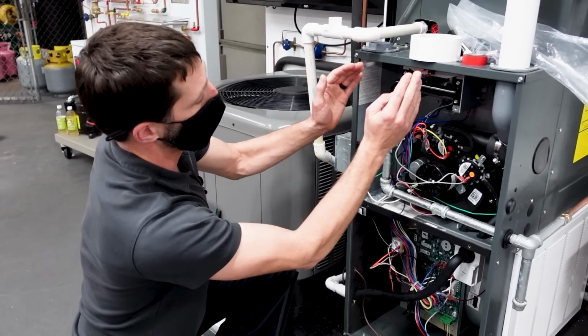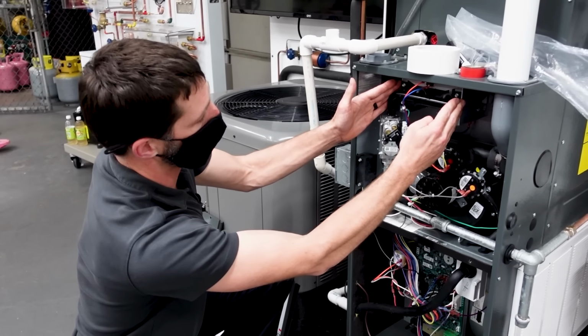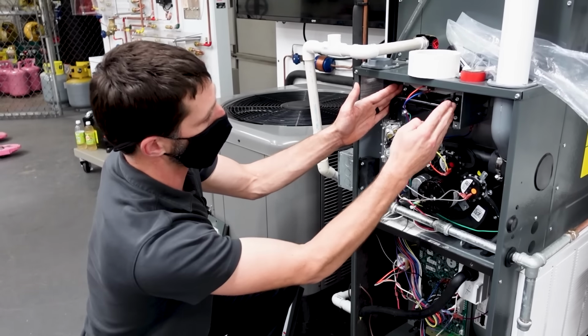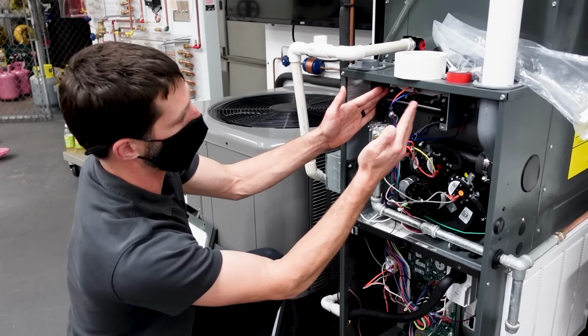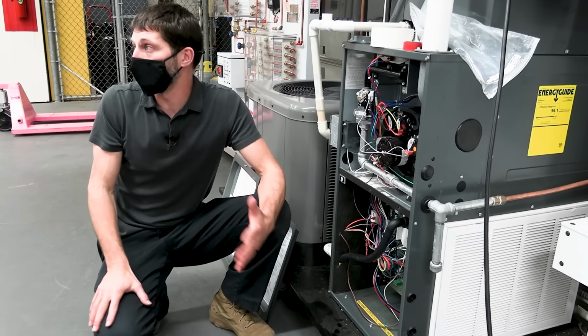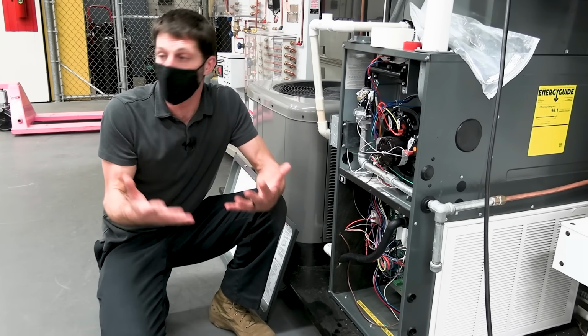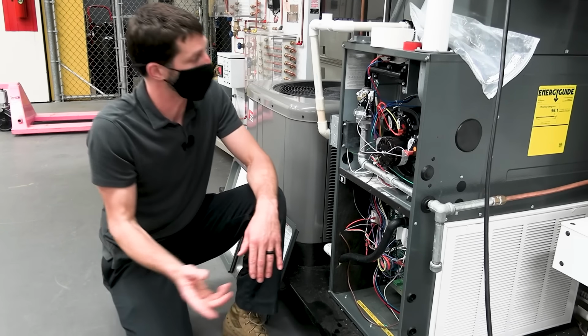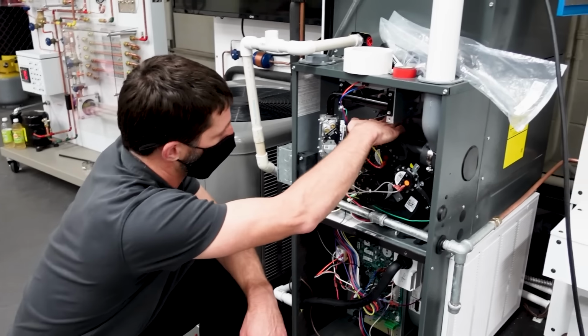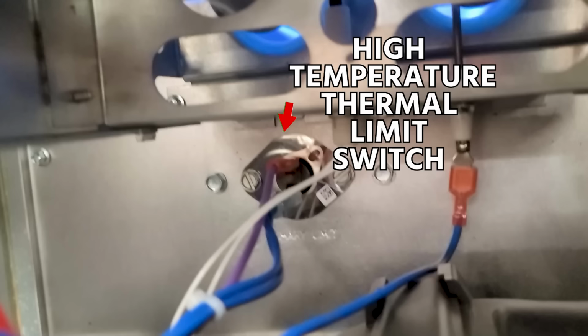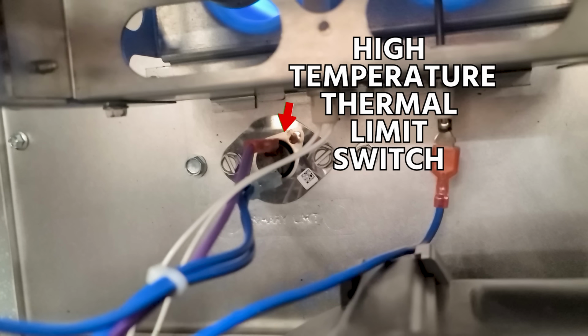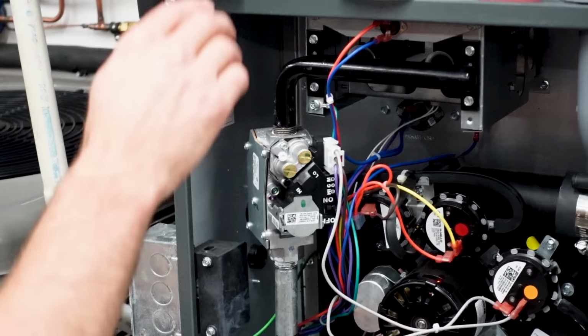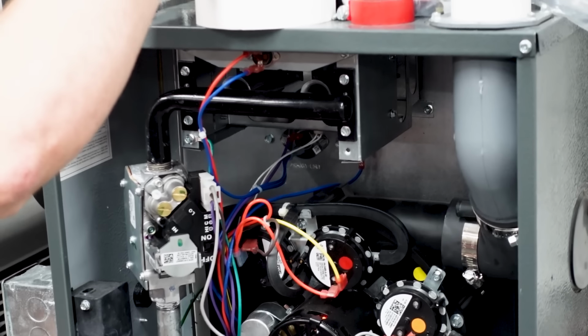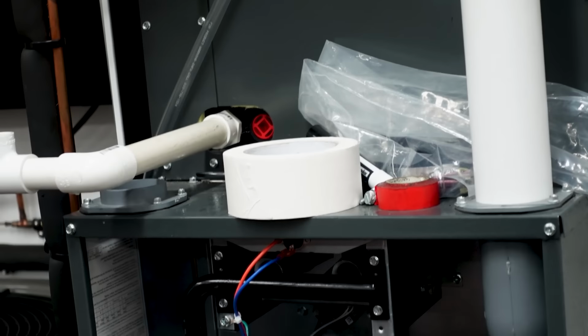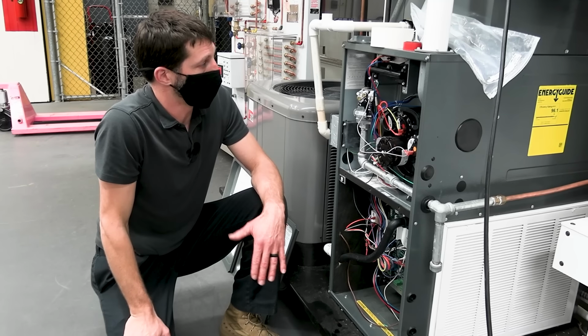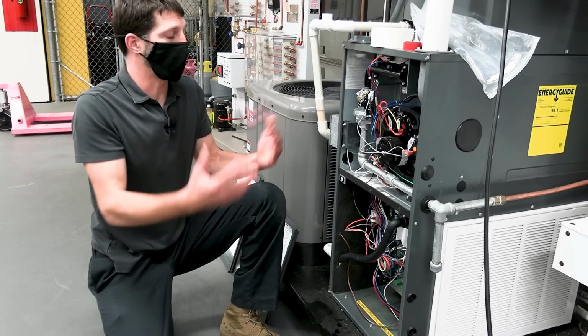So anytime that you're watching this operate, and all of a sudden you hear the blower motor turn on, and then you see the flames start flickering around, that's an indication that you probably have a cracked heat exchanger, and then you've got to do more testing from there, such as turn this off and take out this thermal limit right here, and take a camera in there and see if you can see where the crack is. You can potentially get to it from up above it, up here in the evaporator coil area. You can also take carbon monoxide readings at the supply registers while it's running.